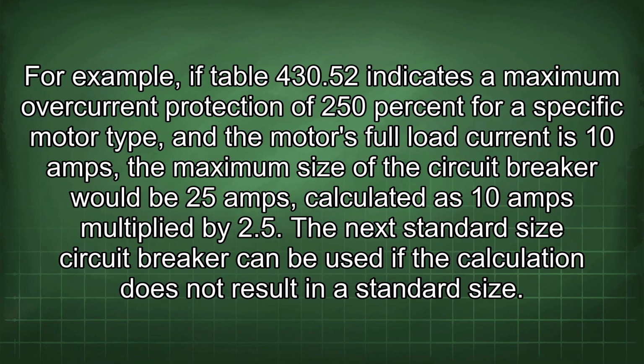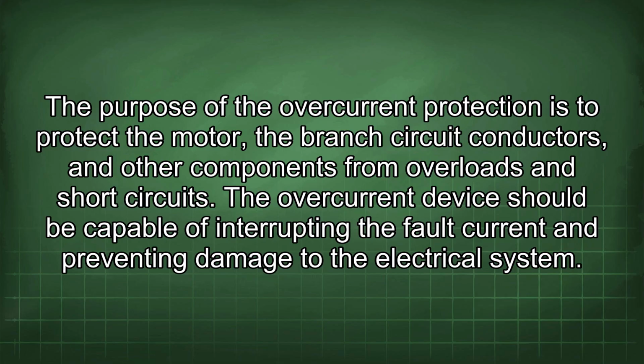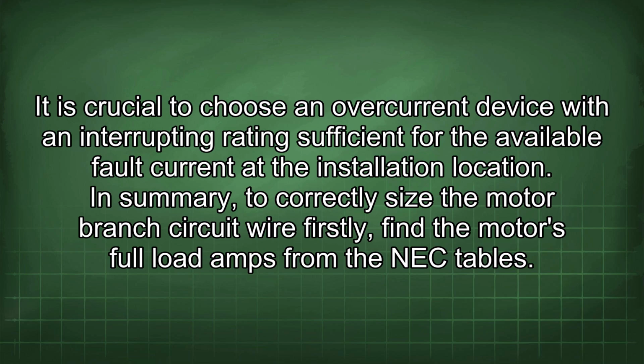For example, if Table 430.52 indicates a maximum overcurrent protection of 250% for a specific motor type, and the motor's full load current is 10 amps, the maximum size of the circuit breaker would be 25 amps, calculated as 10 amps multiplied by 2.5. The next standard size circuit breaker can be used if the calculation does not result in a standard size. The purpose of the overcurrent protection is to protect the motor, the branch circuit conductors, and other components from overloads and short circuits. The overcurrent device should be capable of interrupting the fault current and preventing damage to the electrical system. It is crucial to choose an overcurrent device with an interrupting rating sufficient for the available fault current at the installation location.